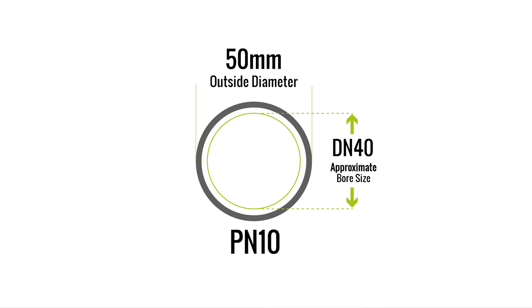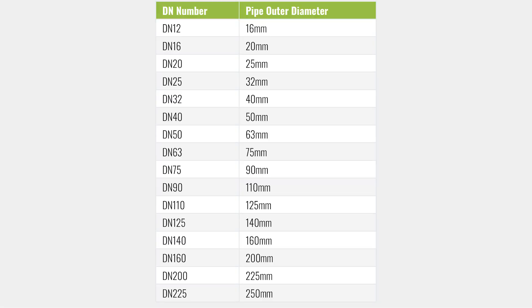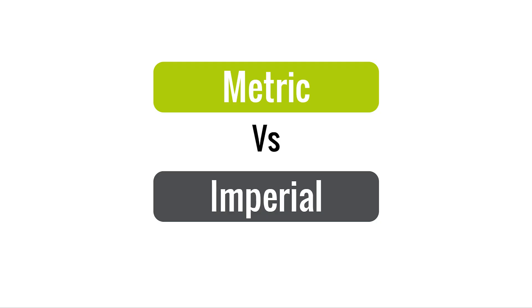In this chart you'll see each DN number with its actual corresponding outer diameter. You'll notice that all DN numbers are rounded to a standard size, but the actual outer diameter is the next standard size up. So a DN 25 is actually 32 millimeters outer diameter, a DN 32 has an OD of 40 millimeters, and as we have already seen, a DN 40 has an OD of 50 millimeters — and this pattern continues.